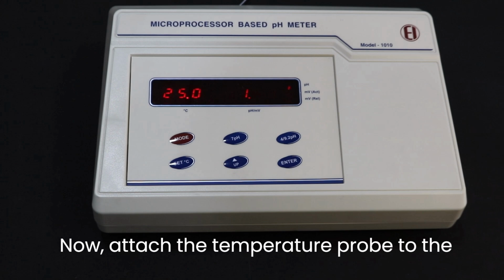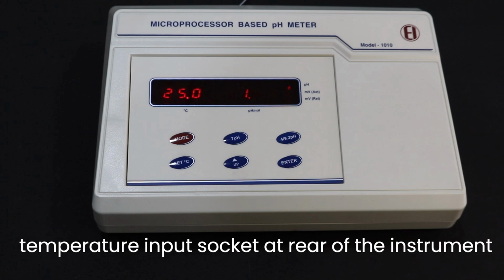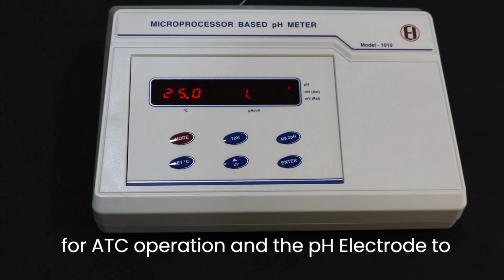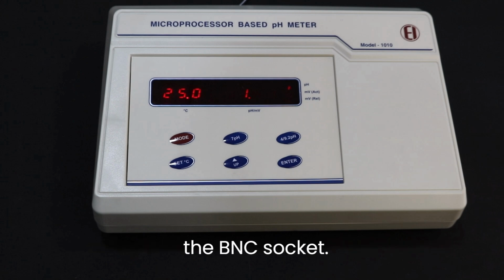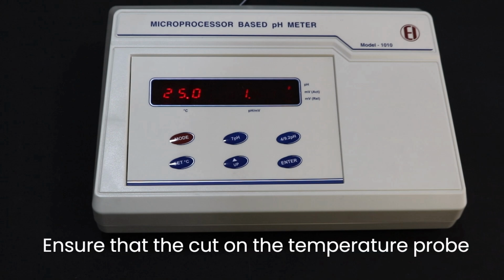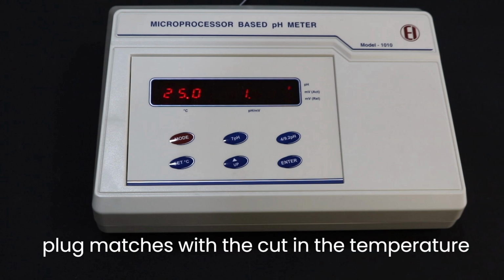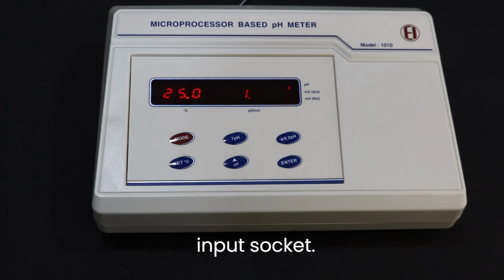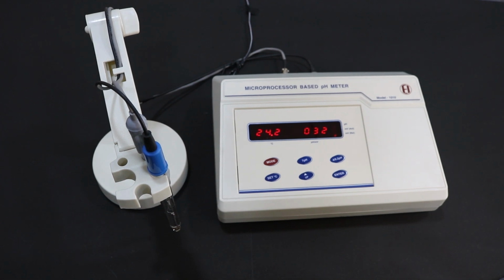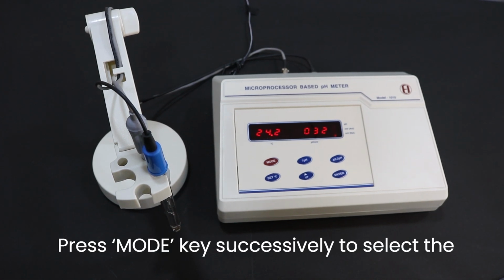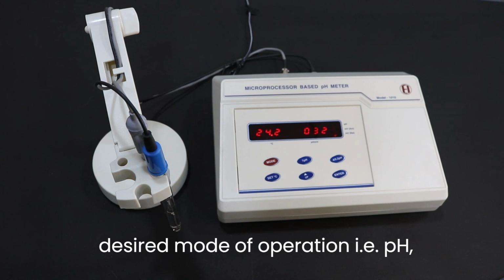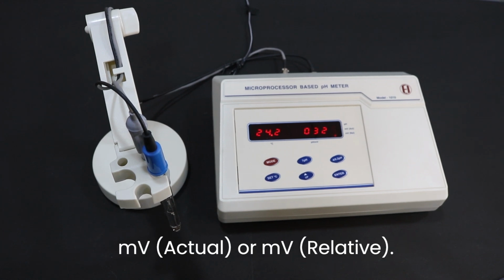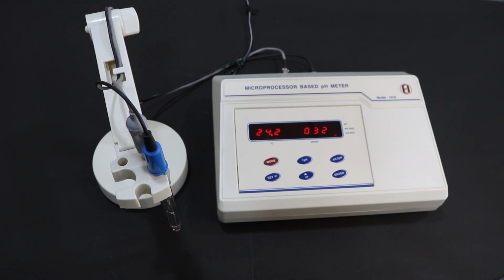Now, attach the temperature probe to the temperature input socket at the rear of the instrument for ATC operation and the pH electrode to the BNC socket. Ensure that the cut on the temperature probe plug matches with the cut in the temperature input socket. Press mode key successively to select the desired mode of operation, that is pH, MV actual or MV relative.